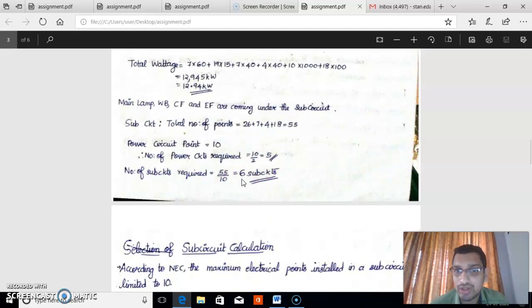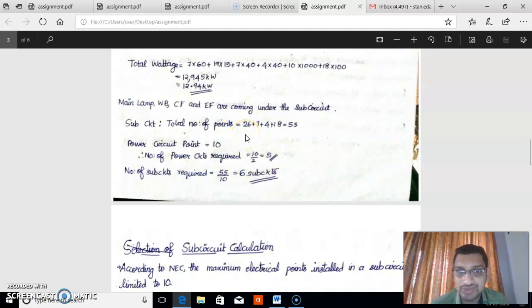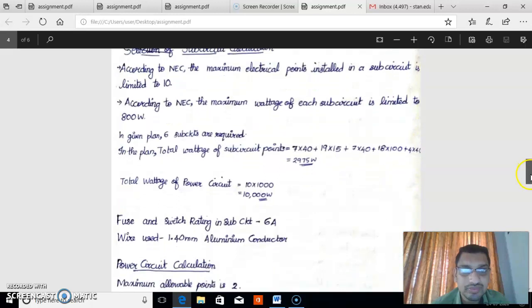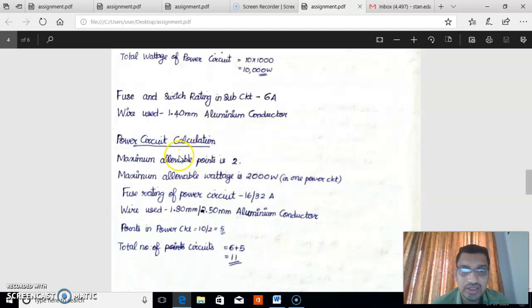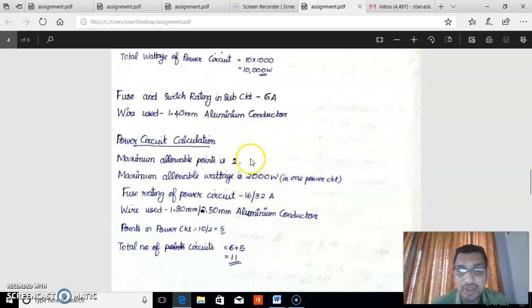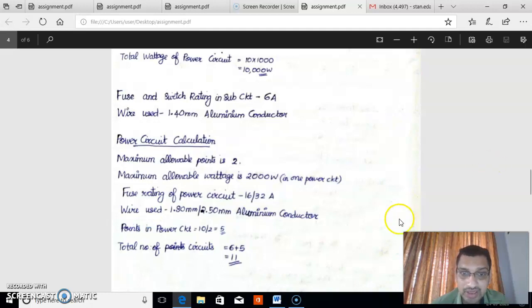Next, we calculate the number of power circuits. In our case, we have 10 power plugs, with a combined wattage of 10 × 1,000 = 10,000 watts. The criteria for power circuits are: maximum 2 points per power circuit, and maximum wattage of 2,000 watts per circuit. With 10 power plugs and a limit of 2 per circuit, we need 5 power circuits (10 ÷ 2 = 5).